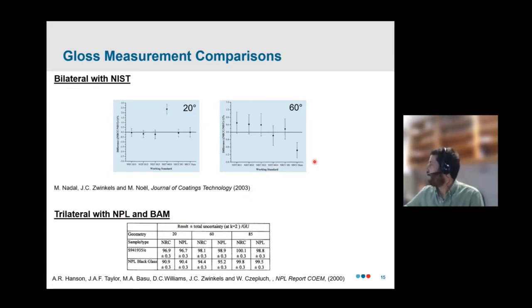And it's a similar story. We did another comparison around the same time involving NPL and BAM. So you do, when you look at this data, you do occasionally see some outlier samples. So there's one in the 20 degrees and one in the 60 degrees. The 60 degree sample, for example, is a haze gloss standard. So we believe it has a slightly more complicated BRDF than just a nice, smooth optical surface. And that kind of, well, that's probably what complicates getting a reliable measurement with that sample.